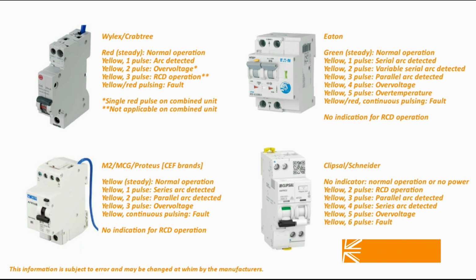Could we not have had some commonality on what colours they were and what they mean? Just look at this Technicolor clusterfuck just between these 4 models here. Normal indication being red on one, green on another, yellow on a third, and nothing on the 4th.